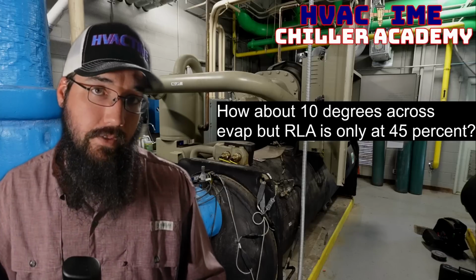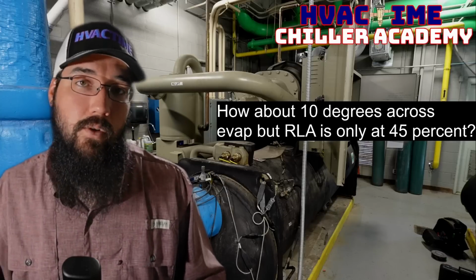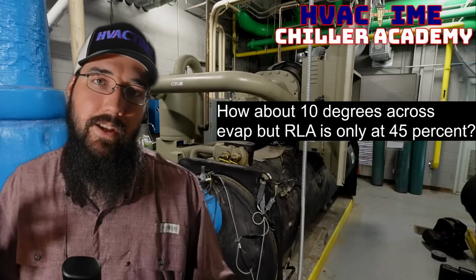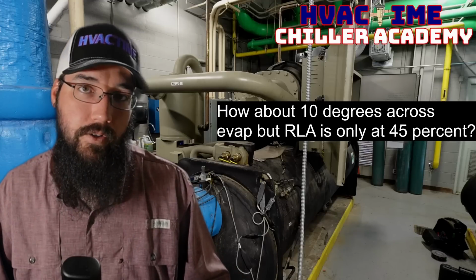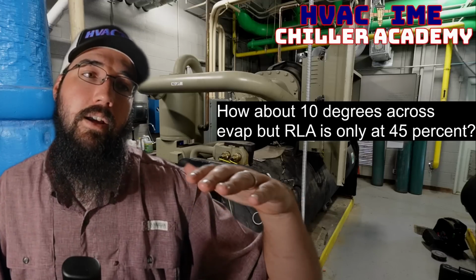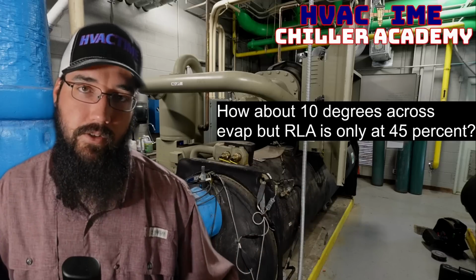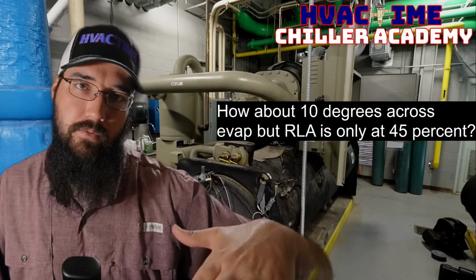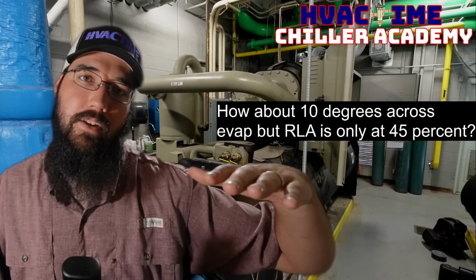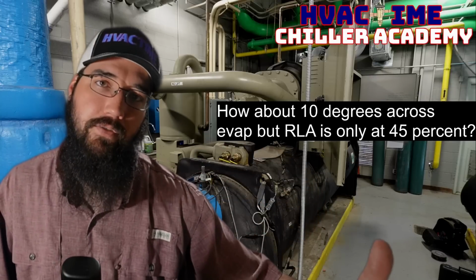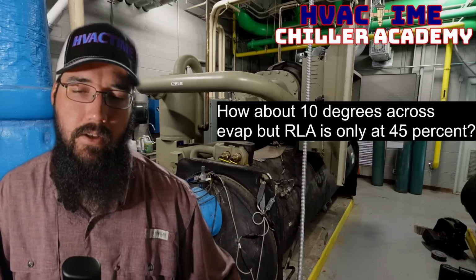Now, the other side of that too is, especially in a water-cooled environment, but even air-cooled ambient, we could significantly reduce our condenser water temperature, or allow our condenser head pressure to drop significantly if we're discussing air-cooled. So basically, instead of allowing the fans to stage to maintain a higher head, we could just allow all the fans to stage on and drop our head significantly.